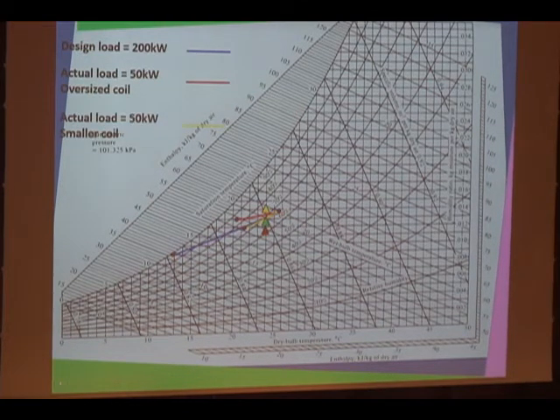So further, it was 100 kilowatts actual installation. It will further reduce because there is a part load operating characteristic of any air conditioning system. Let's remember, it's never a fixed value. It's never as designed. Loads change all the time. So here you're looking at a case where the 100 kilowatts further becomes lower, 50 kilowatts. Blue is what we designed for as a 200 kilowatts coil. The same large coil comes off with the red line.